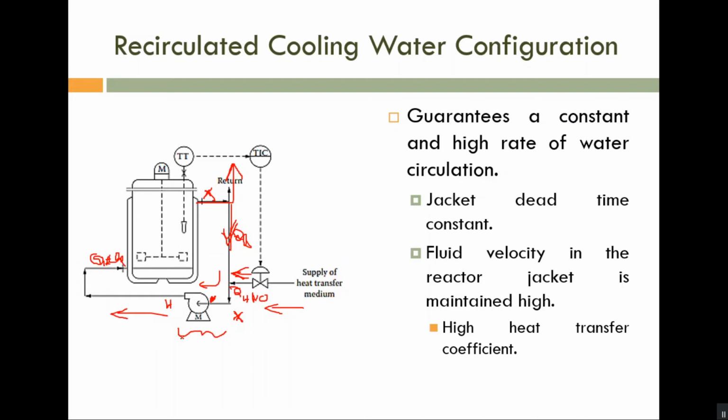So please note, the flow rate is constant now, or the variation is negligible now through this shell. Only heat energy is varying. The effective heat energy is varying. Is it okay? So what is the advantage? The variation of Reynolds number problem is avoided. Variation of process dynamics is avoided, etc.